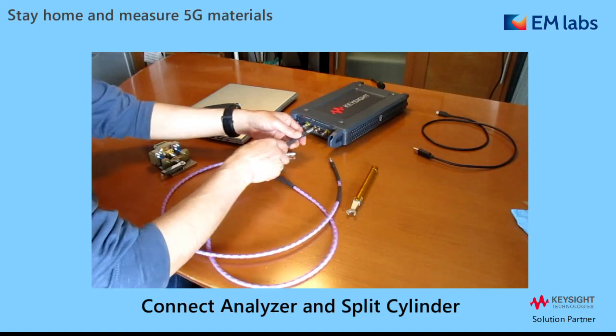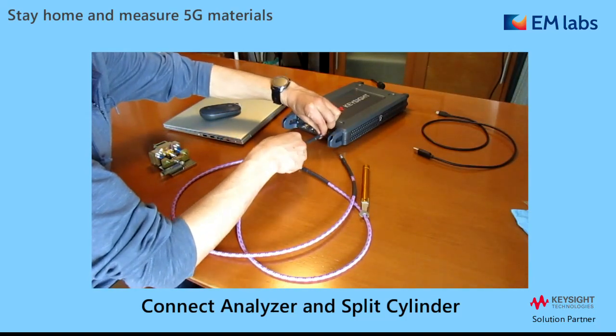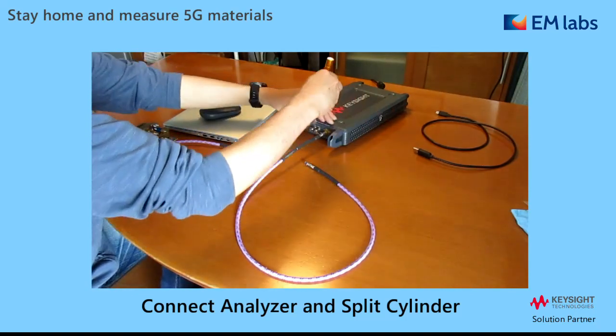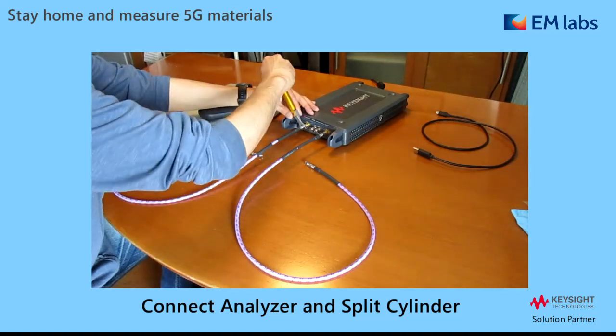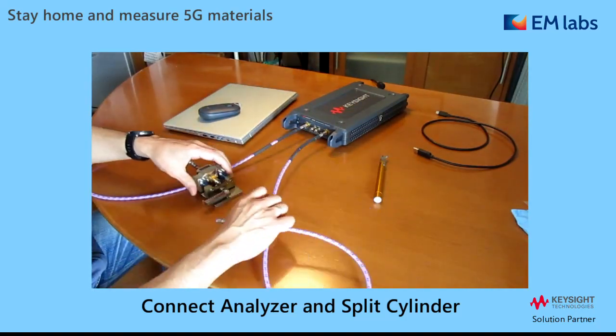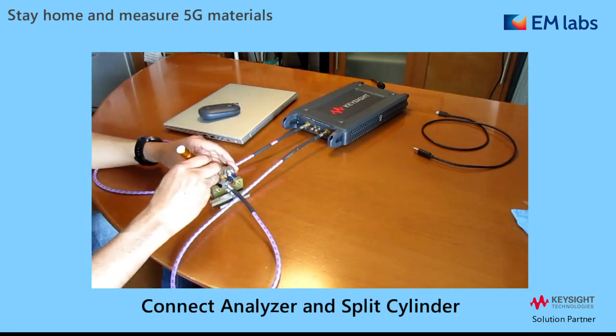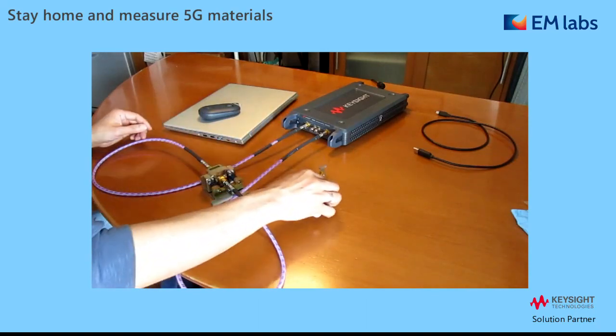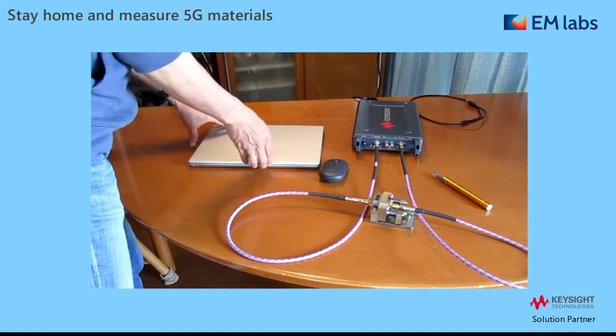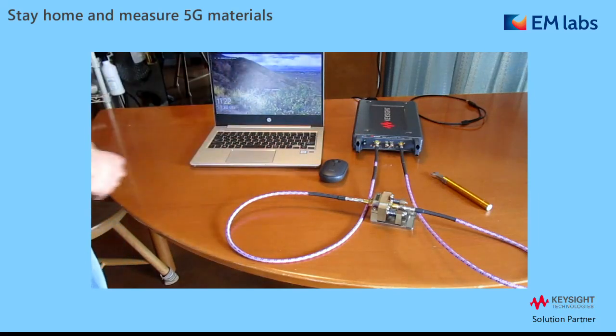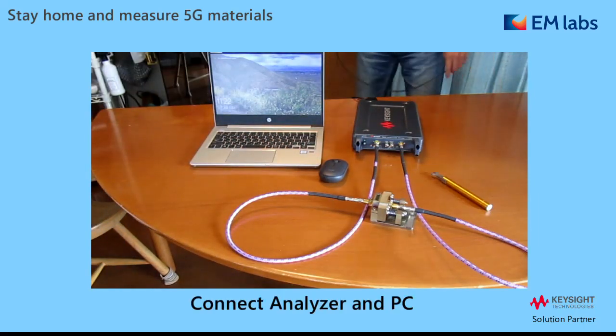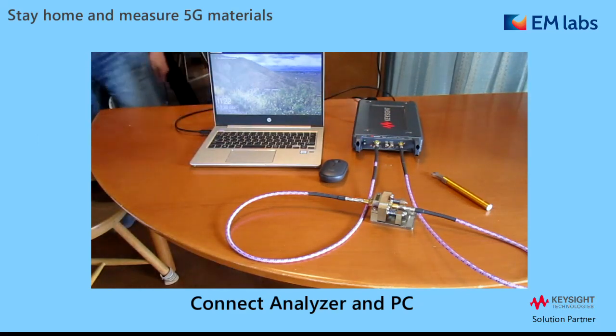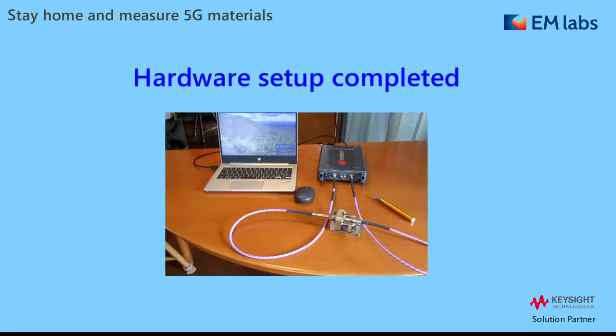First, connect the network analyzer and split cylinder with RF cables. The connection affects measurement results, so I carefully connect using the torque wrench. Digital connection is pretty simple — we just need one USB cable. Hardware setup is completed already.